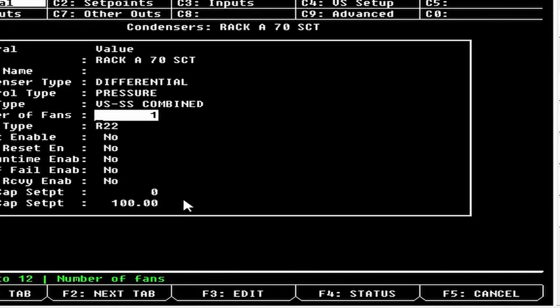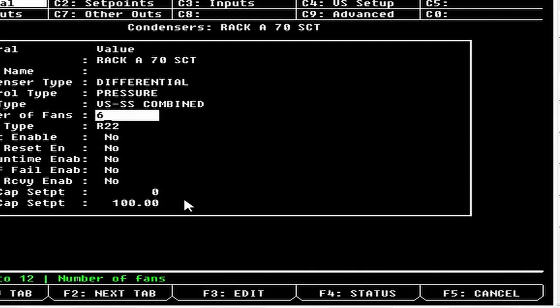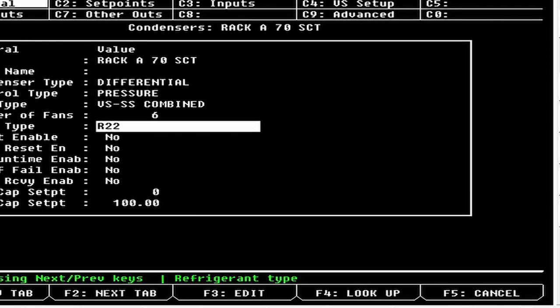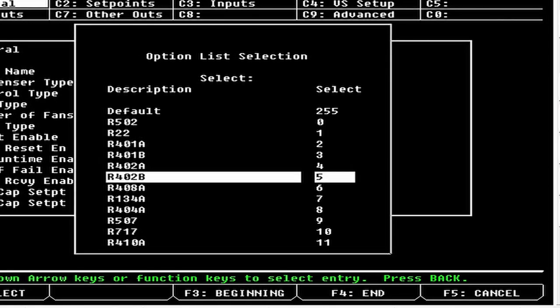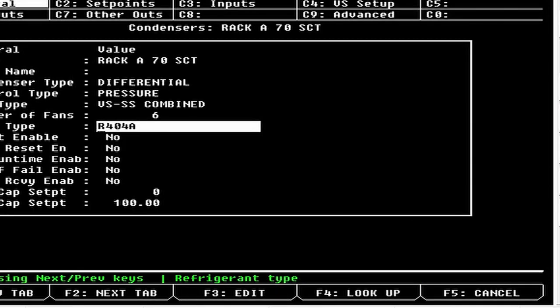For number of fans, we'll go six fans — you choose based on how many outputs you have. A lot of condensers have a fan splitting relay, so say you have a 10-fan condenser; you won't control all 10 because you'd need two boards with only 8 outputs each. With a split relay you only need 5 outputs. We're going to go six, which would represent a 12-fan condenser. For refrigerant type, hit F4 Lookup — we're going to choose 404A today.